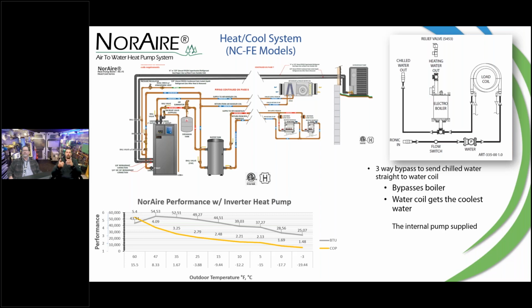I want to put an indirect on this guy and utilize that 20 kW boiler inside there. If there's a call for domestic hot water, it's going to turn off that heat pump 100% and just dedicate that electric boiler to my domestic hot water. So if we're integrating all of that stuff, we definitely put together a pretty cool package. Now we could do heat pump condenser to an electric boiler as a preheater.